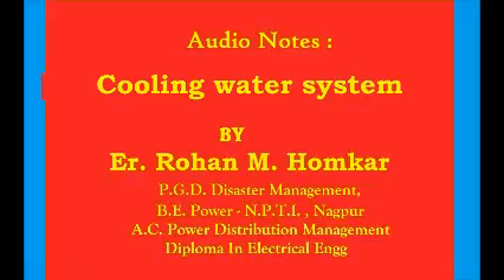Now, condenser water cooling systems. The cooling systems which are commonly used in practice, according to the availability of water, are listed below. The cooling system is divided into open or once-through system, second is a closed system, and third one is a mixed system. Now the closed system is divided into water cooling or air cooling. In the water cooling section, the closed system is divided again into cooling ponds and cooling towers. In the air cooling system, it is divided as a closed system, direct dry type cooling tower system, or indirect air cooling system.